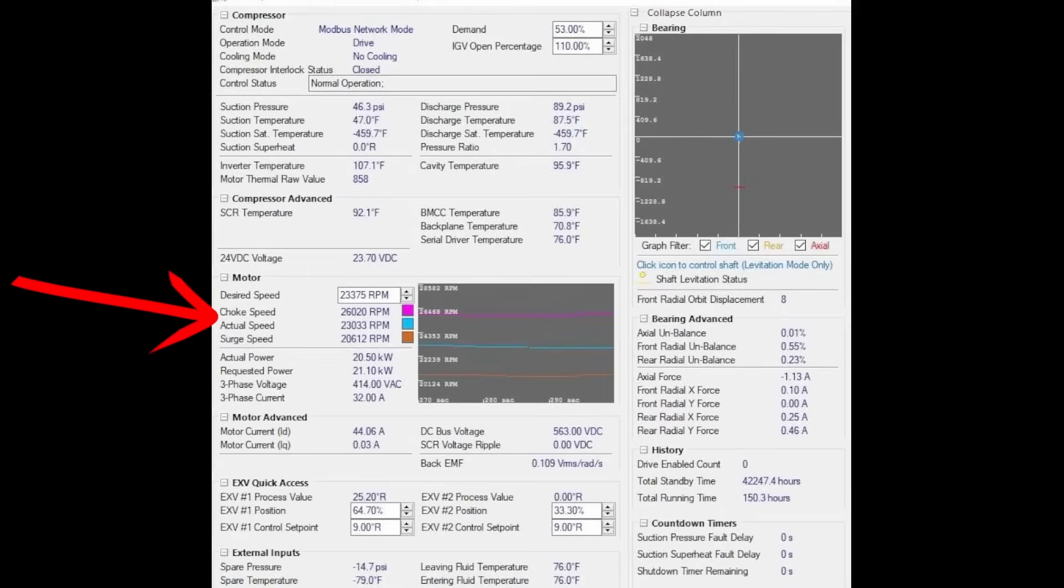The reason that the surge is lower is because these set points are dictated based off of this ratio. So as this ratio increases, these speed thresholds will increase, and as this ratio decreases, these speed thresholds will decrease. This will be a constantly fluctuating point based off of this pressure ratio.